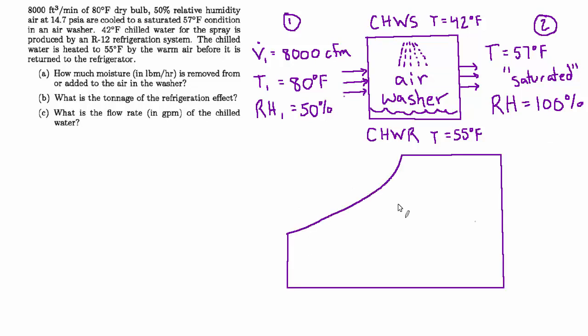So state one is somewhere about here, 80 degrees and 50% humidity. And state two is somewhere around here, all the way up against the saturation curve, but it is actually just a bit lower than state one. If we take both points all the way over to the right axis where we would find the humidity ratio, we will find that the humidity ratio at state one is greater than the humidity ratio at state two. So even though the relative humidity is increasing, the humidity ratio is lower at state two.